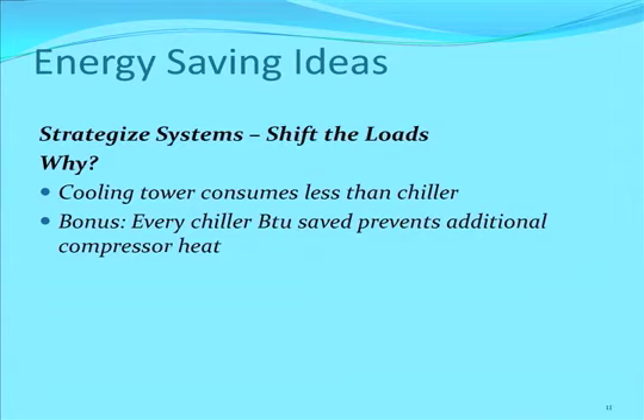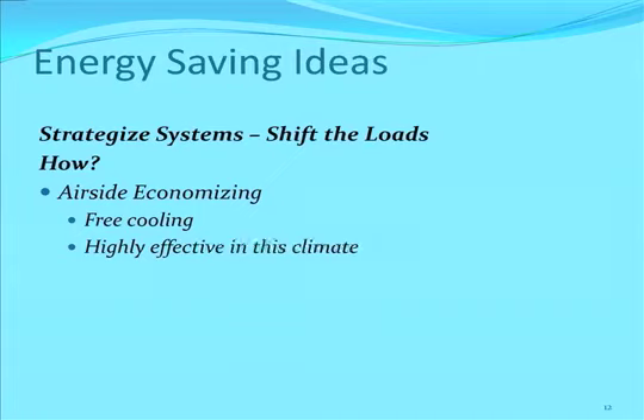Next, we're shifting the loads, so matching the loads, then going to shifting the loads. Mainly what I mean here is you've minimized your loads and you've done what you can to match the equipment to the loads. Now you want to shift the cooling to as efficient a way as you can do it. How do we do that? The first one, like I said, airside economizing always comes up as a prime candidate. If you can cool with your outside air, you don't need to run your chiller, you don't need to run your cooling tower, at least not as much. And in this climate, it's exceptionally good.